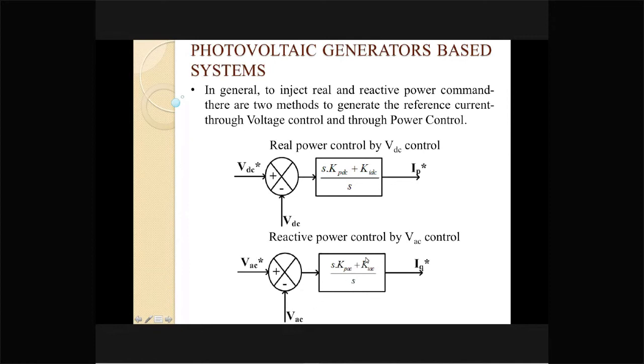Generally, this PI mode operation is not followed because ultimately this reactive power will hit the upper limit many a time. So droop mode is generally considered, but yes, in some cases we can go for this if the photovoltaic system is a park, like you can assume that it is a 300 or 400 megawatt solar park having higher capacity of inverters.